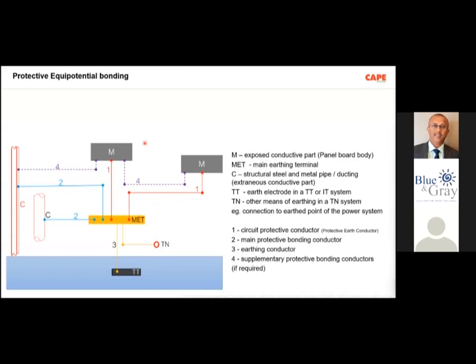So basically all the metal parts in your building are interconnected to a bus bar. That particular bus bar is connected to an earth electrode if you have a TT system, and it is connected to the source neutral of the transformer or DG if you go for a TN-S system or a TN system. So basically for industrial and commercial installation, we are supposed to follow the TN system. For a TN system, the bus bar in your building at the main distribution board must be connected back to the source, not to the earth electrode in soil. And this is called protective equipotential bonding.